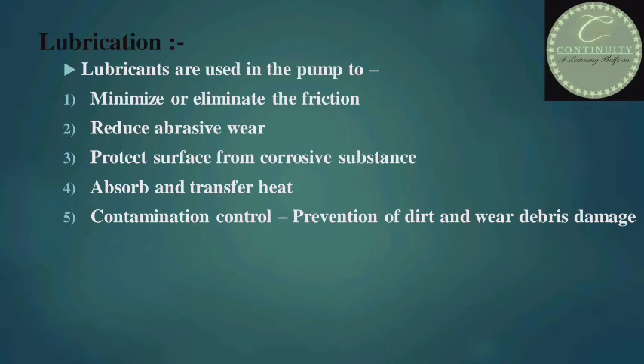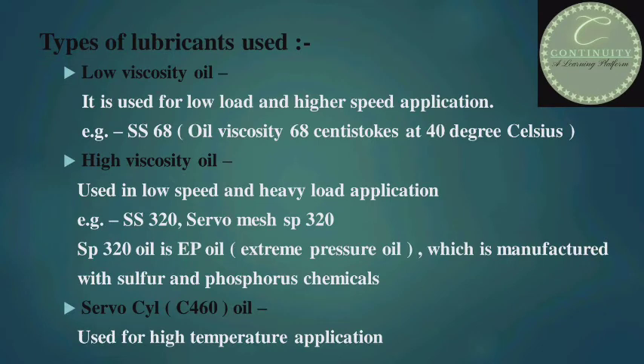Now, lubrication of the centrifugal pump. Lubricants are used in the pump to minimize or eliminate friction, reduce abrasive wear, protect surfaces from corrosive substances, absorb and transfer heat, and control contamination — that is, prevention of dirt and wear debris damage. Various types of lubricants are used in the pump. Low viscosity oil is used for low load and higher speed applications, such as SS68 — Servo System 68 — with oil viscosity of 68 centistokes at 40°C.